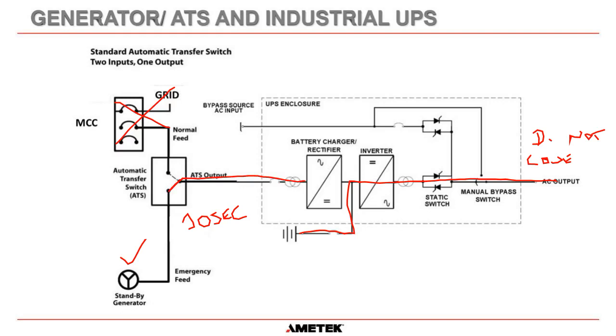So they're ready if, for example, let's say the standby generator fails, or you need to do something with the fuel. Then what you can do is you can stop the generator, or it's stopped automatically. We'll go back on battery power, and then you can do whatever you need to do to your standby generator while the batteries supply the load circuits. Okay.